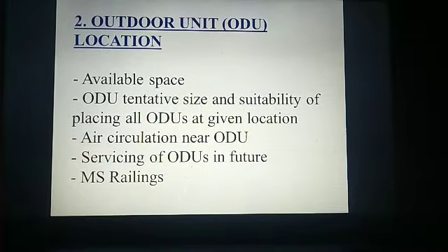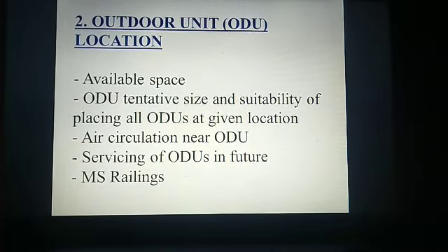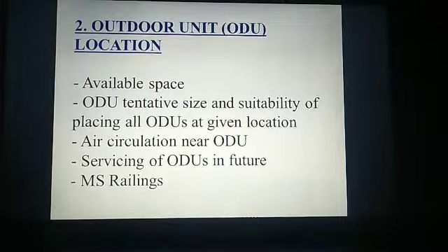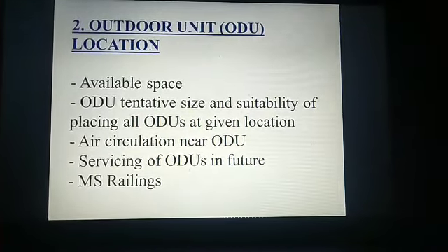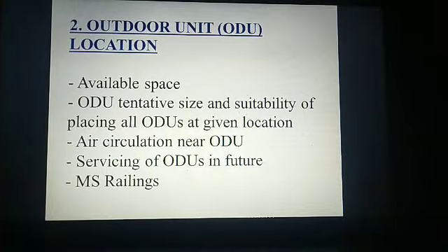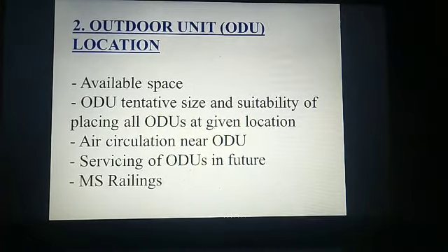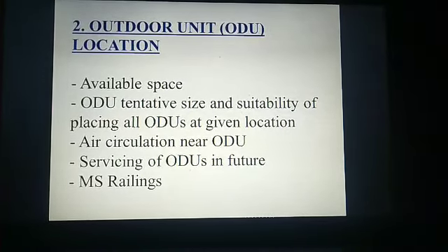Also check whether outdoor unit location is feasible in terms of servicing point of view. Ask for MS railings for outdoor units wherever needed. Outdoor unit location should be selected in such a manner that minimum copper pipe can be utilized.